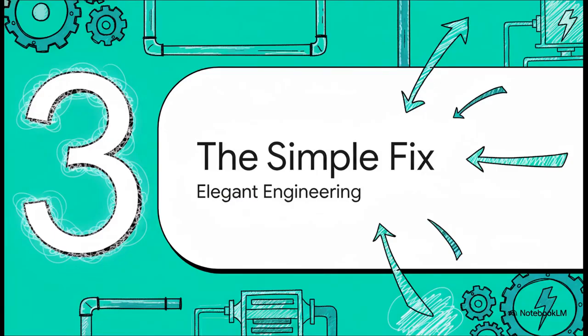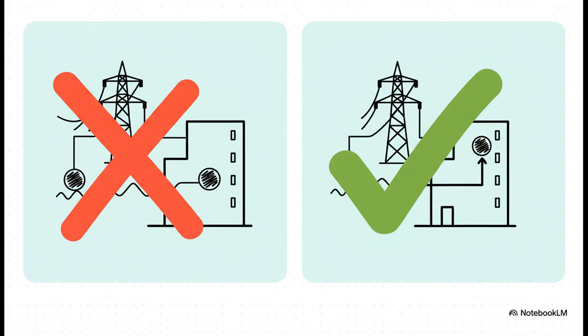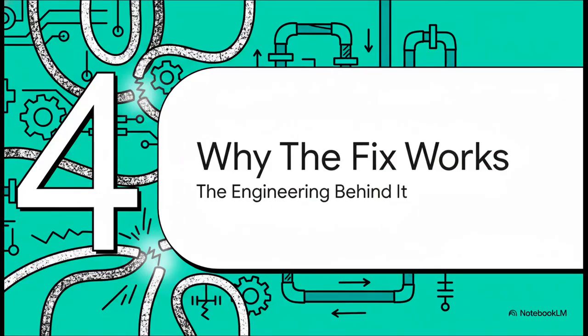So how do you solve such a deep, fundamental problem? This is the best part: the solution is almost frustratingly simple, but incredibly elegant. The fix is to just move the sensors. Instead of measuring that tiny, jumpy amount of power coming in from the grid, you move the CTs to measure the building's total electrical load. You stop trying to control the grid connection and start responding to what the building is actually using. It's a night and day difference. It's just a small change in wiring, but it completely changes the system's behavior.